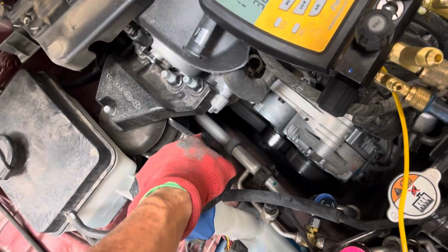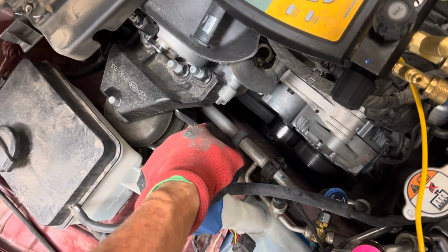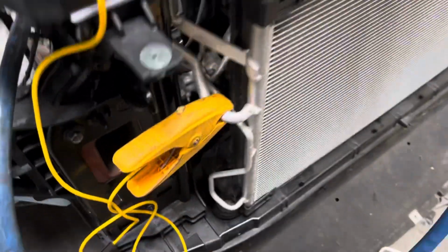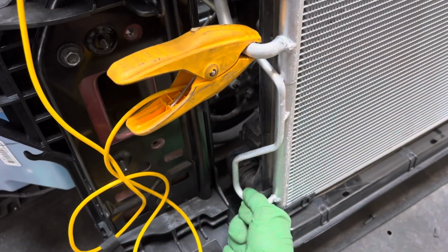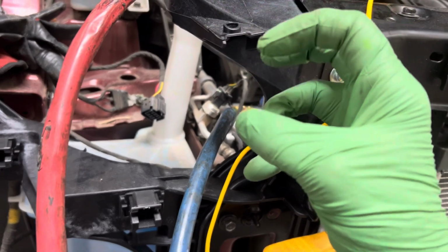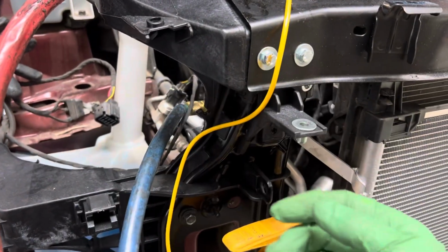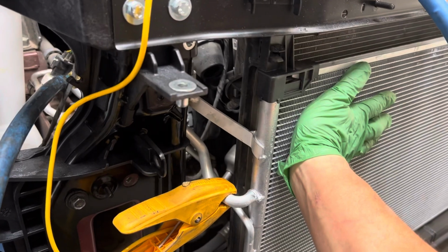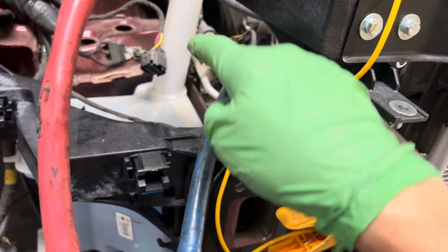So that internal heat exchanger is doing a lot of work of removing heat out of the liquid line. Remember, our liquid line right here was 92 degrees. And we have 92 degrees going in, and then the heat is being absorbed out of the liquid into the suction line to deliver that heat back to the compressor to reject it through the condenser. But on the other side, the liquid line will drop temperature.